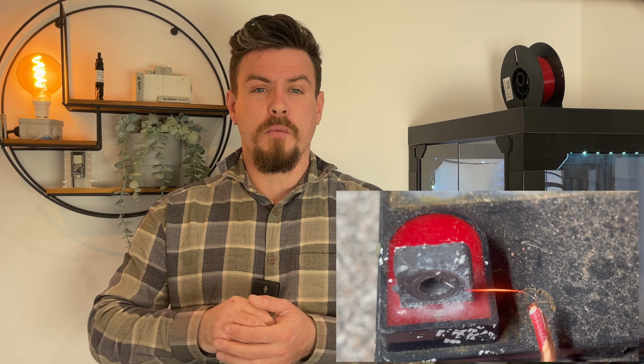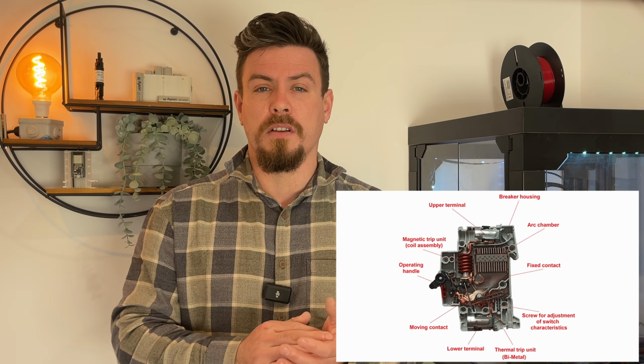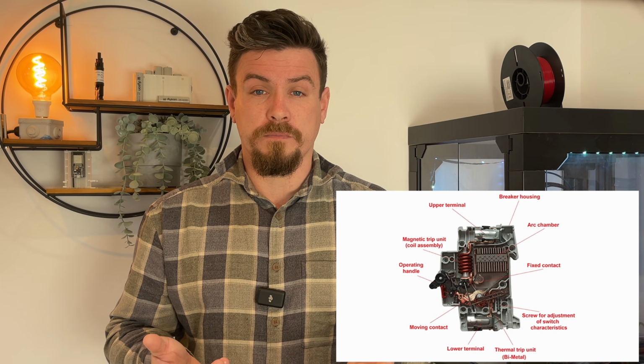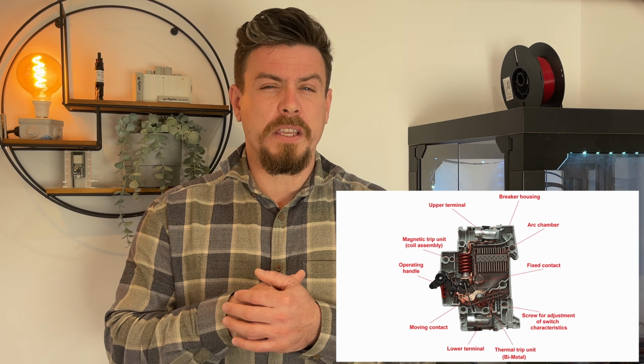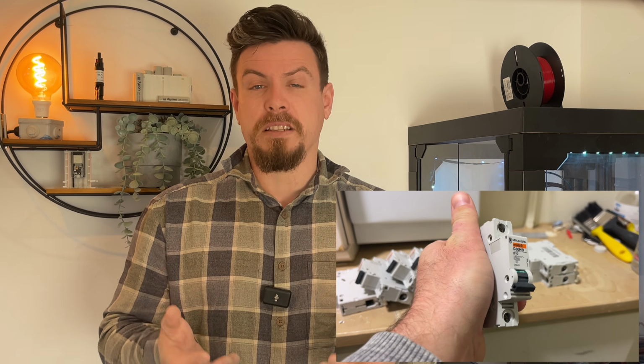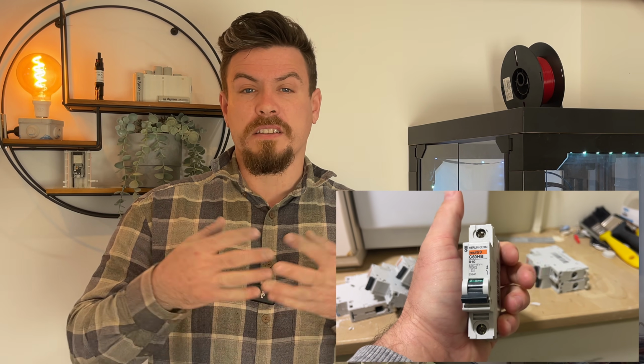Some of these effects we looked at a couple of weeks ago when we talked about how we would design a circuit and choose the correct cable and protective device. Remember, we talked about how the cable would run through insulation and how that would affect the rating of the cable, effectively downrating that cable. So we needed to make sure that we had a cable that would stay within the correct temperatures. I'll pop a link to that up here if you haven't already seen that.